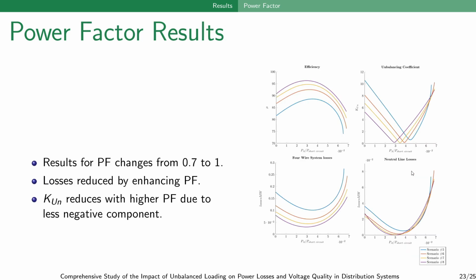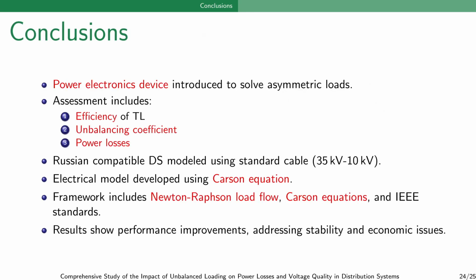Power factor results. Here we present the results when the power factor is changing from 0.7 to 1, creating scenarios 5, 6, 7, 8: 0.7, 0.8, 0.9, and 1, which we can show here. Enhancing the power factor reduces the power loss and decreases the unbalancing coefficient. That means improving the overall system performance.